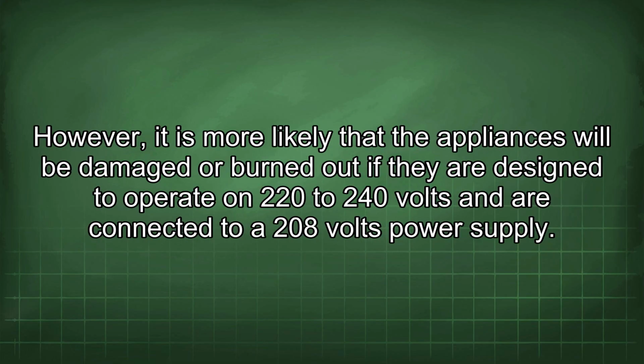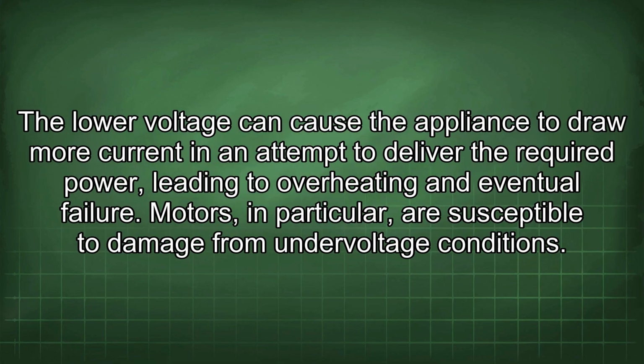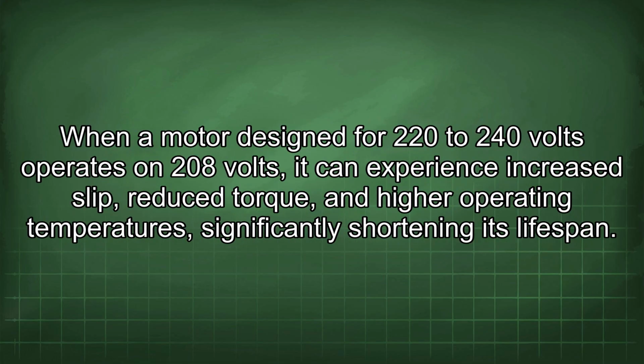However, it is more likely that the appliances will be damaged or burned out if they are designed to operate on 220 to 240 volts and are connected to a 208 volts power supply. The lower voltage can cause the appliance to draw more current in an attempt to deliver the required power, leading to overheating and eventual failure. Motors, in particular, are susceptible to damage from under-voltage conditions. When a motor designed for 220 to 240 volts operates on 208 volts, it can experience increased slip, reduced torque, and higher operating temperatures, significantly shortening its lifespan.